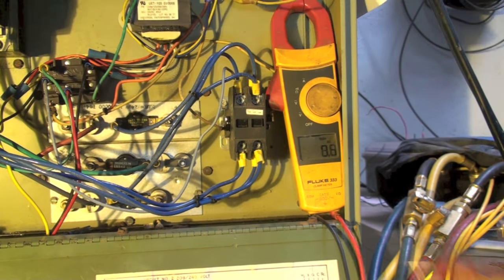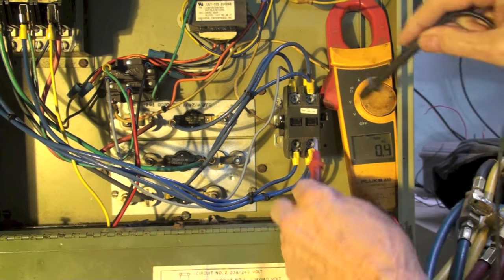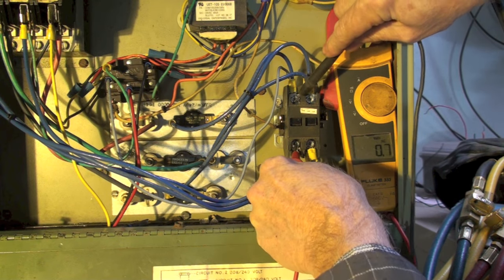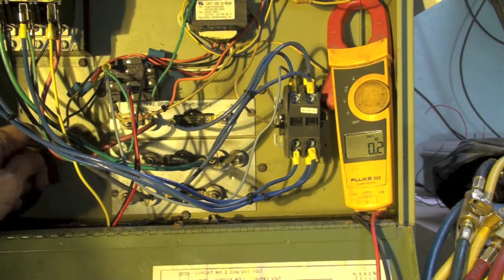I'm going to check across here. I'm reading zero volts. Okay, I'm going to take one wire coming in and here's the other wire coming in. Okay, 242.